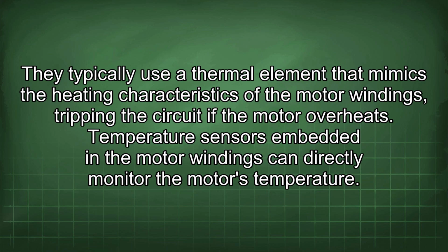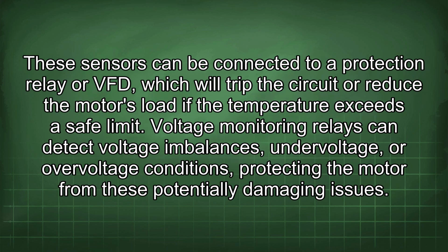They typically use a thermal element that mimics the heating characteristics of the motor windings, tripping the circuit if the motor overheats. Temperature sensors embedded in the motor windings can directly monitor the motor's temperature. These sensors can be connected to a protection relay or VFD, which will trip the circuit or reduce the motor's load if the temperature exceeds a safe limit.